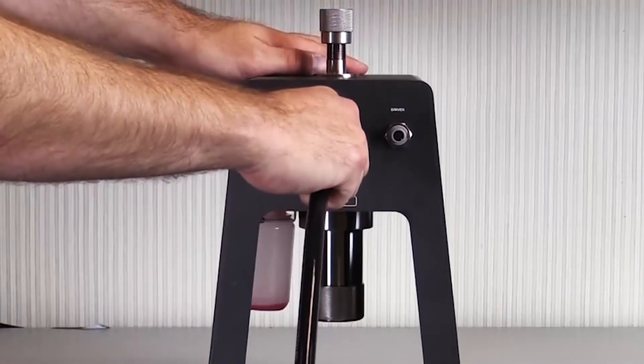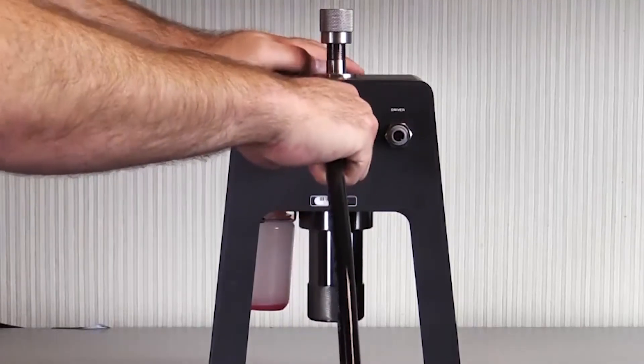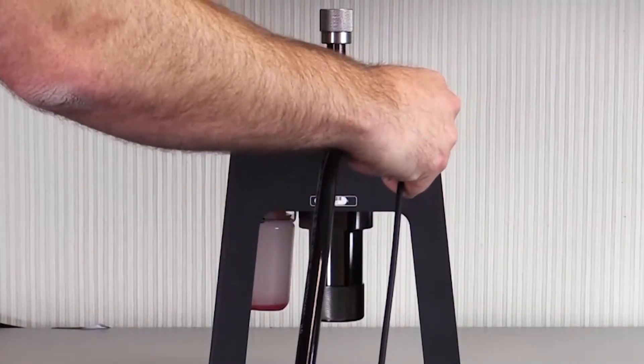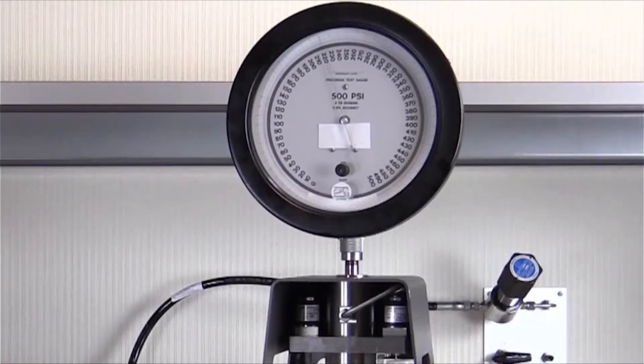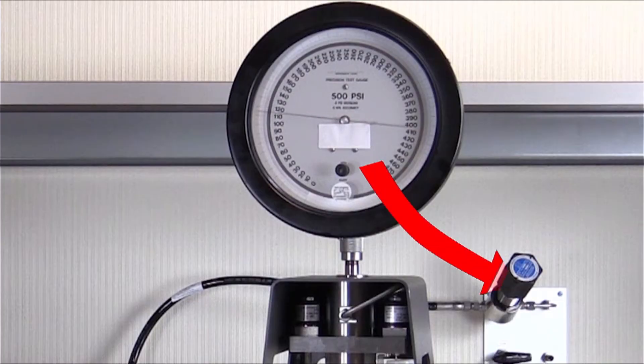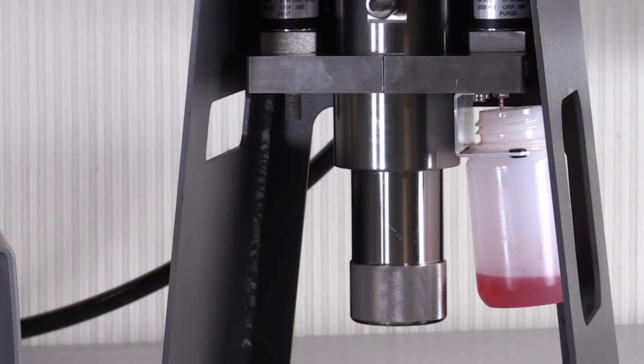Simply connect the CPS to the test port and electronically to the valve driver connection on the back of the 2271A. The 2271A will now use the CPS to control pressure down, protecting the 2271A by having unidirectional flow away from the controller, as well as a built-in gravity trap and dual-stage filter system.